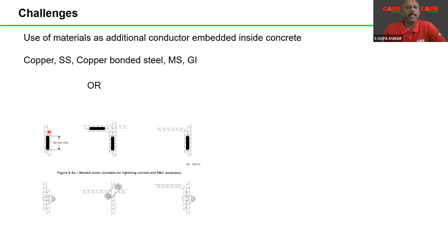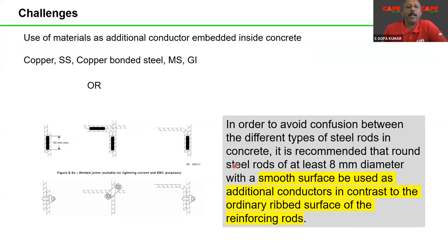Similarly, the standard also recommends, or in the picture it also included, to use the rebar itself. You can use an additional conductor such as copper, stainless steel, copper bonded steel, MS or GI, or you can also use the rebar itself with some kind of special clamping, special welding and so on. But the standard also recommends: in order to avoid confusion between different types of steel rod in concrete, it is recommended that a round steel rod of at least 8 mm diameter with a smooth surface be used as additional conductor in contrast to the ordinary ribbed surface of the reinforcing rod.